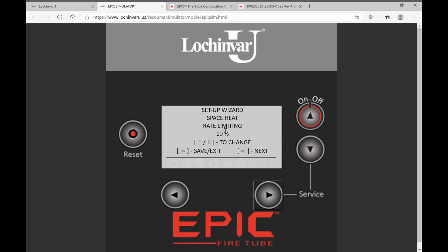Space heat rate limiting. This is an interesting feature. It allows us to minimize or limit the modulation of the boiler. Right now this boiler has a 10-to-1 modulation, so anywhere from 10% to 100%. We can put this down to a maximum of 90%, 80%, 55%. It really depends on what you're going for. For example, on the combi boilers, let's say you need a lot of hot water but not a lot of heating. So you're going to limit this on the heating side.